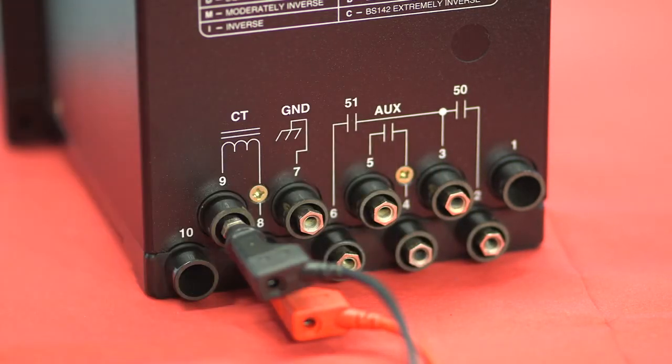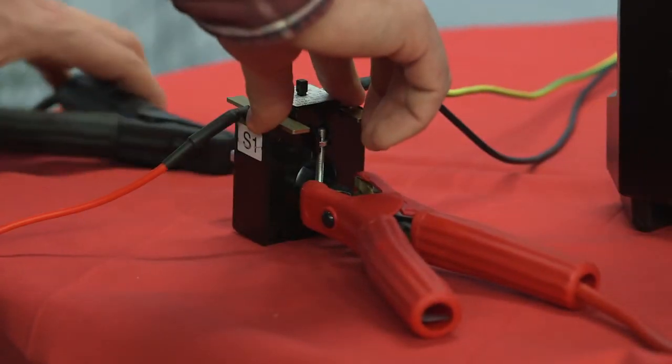During this demo, the CT in the relay will simulate part of a substation. Connect I out to the CT's primary side using the high current cables and clamps. Connect the red cable to the P1 and the black one to P2.